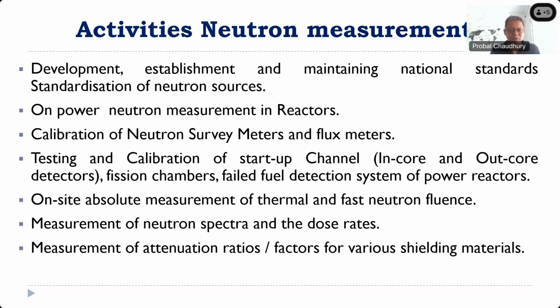Then measurement of neutron spectrum. So the entire neutron spectrum can be measured, and the dose rate can be evaluated: how much dose is being received by that particular neutron field or neutron source. And of course, measurement of attenuation, like in protection level, we had attenuation for gamma. Here we have measurement of attenuation for neutrons. We have different shielding materials for neutrons.